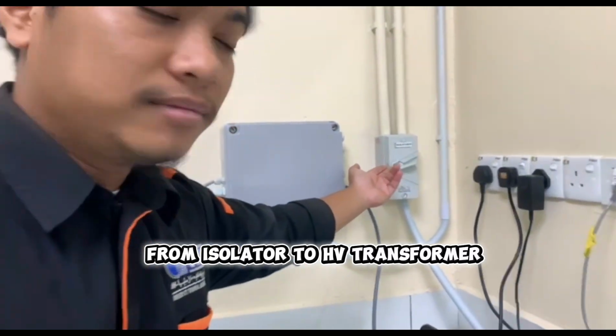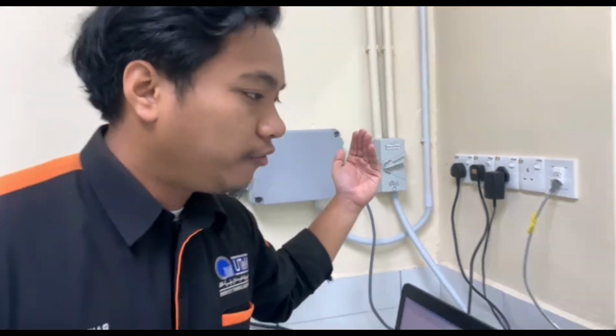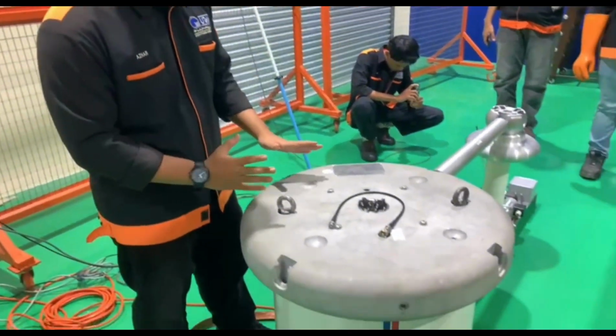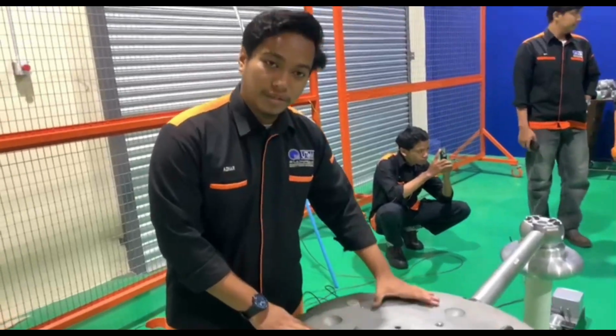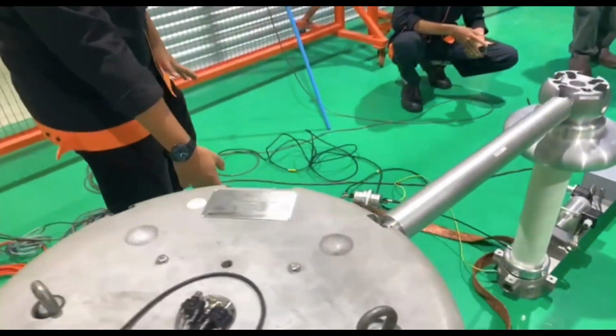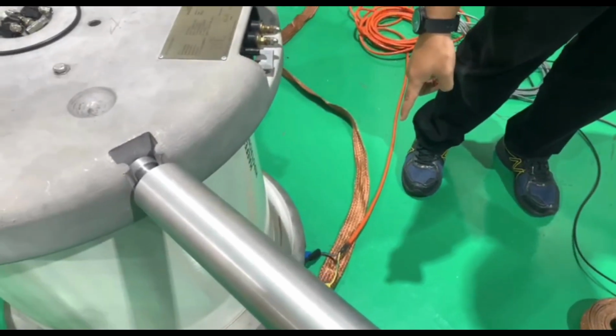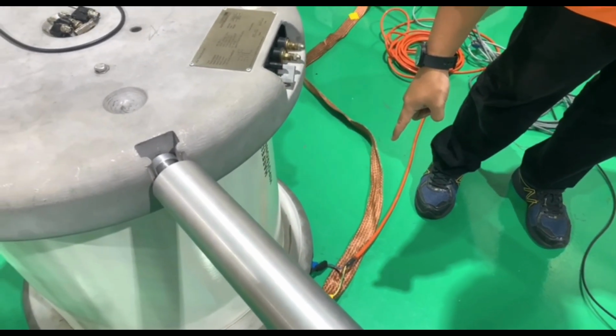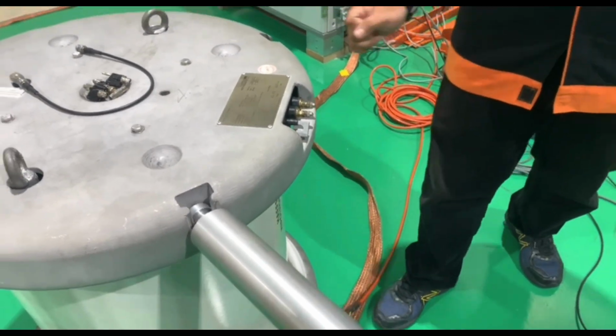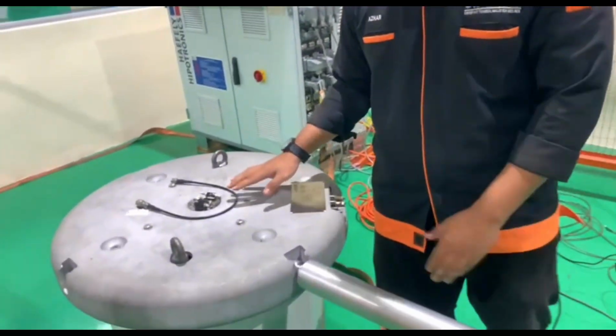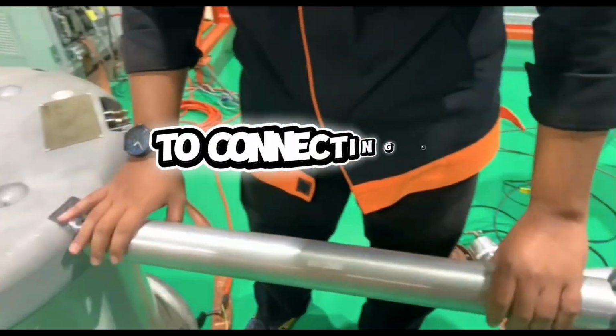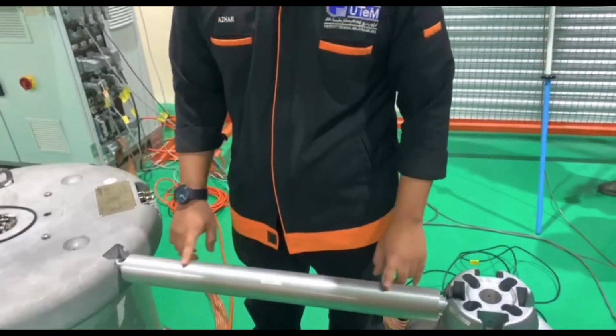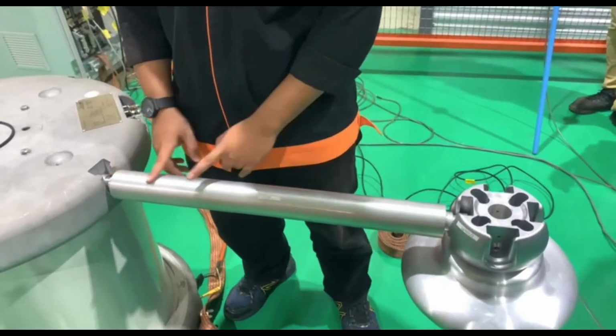This is the isolator. The isolator will give full supply for the equipment inside the lab, and this supply goes to the high voltage transformer. This is the wiring, you can see it has a DIN, power supply line, and neutral. The isolator gives the full power supply to the high voltage transformer, and then we have the connecting rod, which connects the high voltage transformer to the connecting cup.